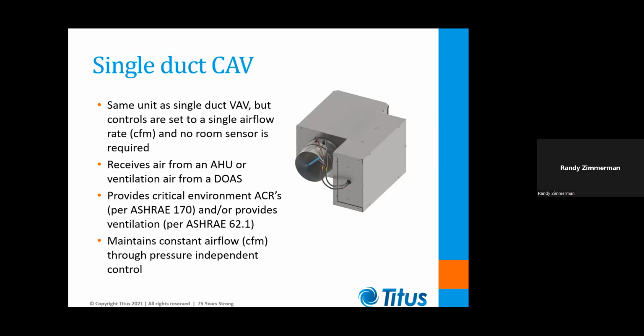Now we can take that same box and we can set the minimum and maximum airflow rates to the same value, and it becomes a constant volume box. Now, of course, if we're going to do a constant volume box, we can't control room temperature that way. So we would have to put some kind of a coil on the box so that if we can't control the room temperature with air volume, then we're going to have to do it with air temperature. So then we would be taking our 55-degree air from the air handler and reheating it in order to maintain temperature control in the room.